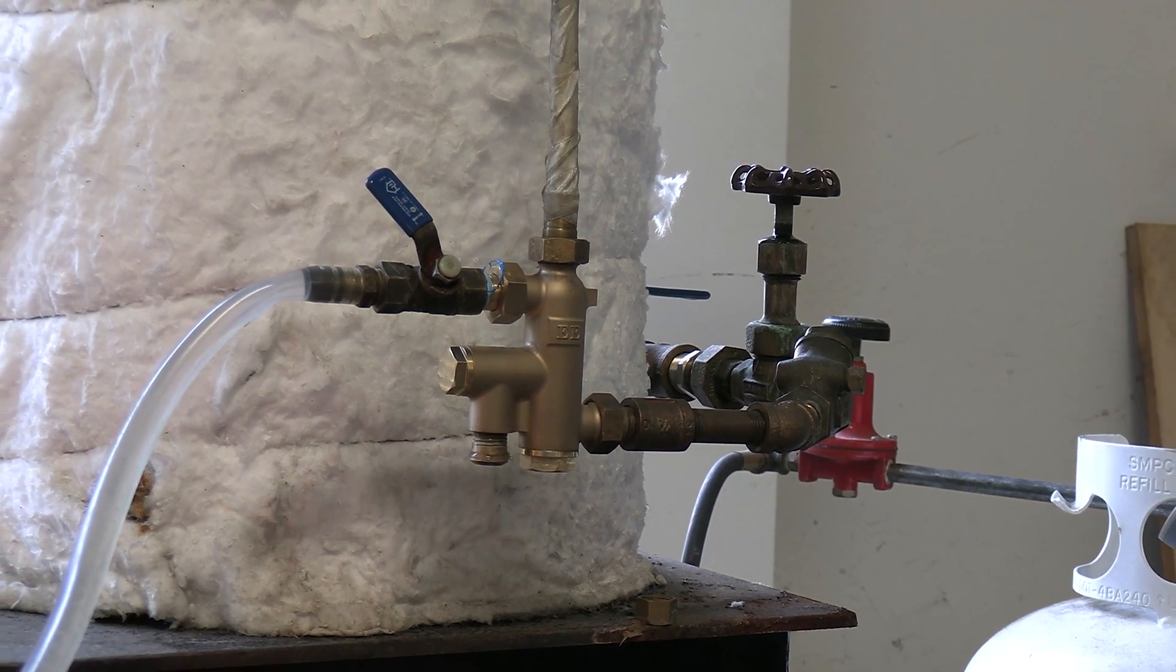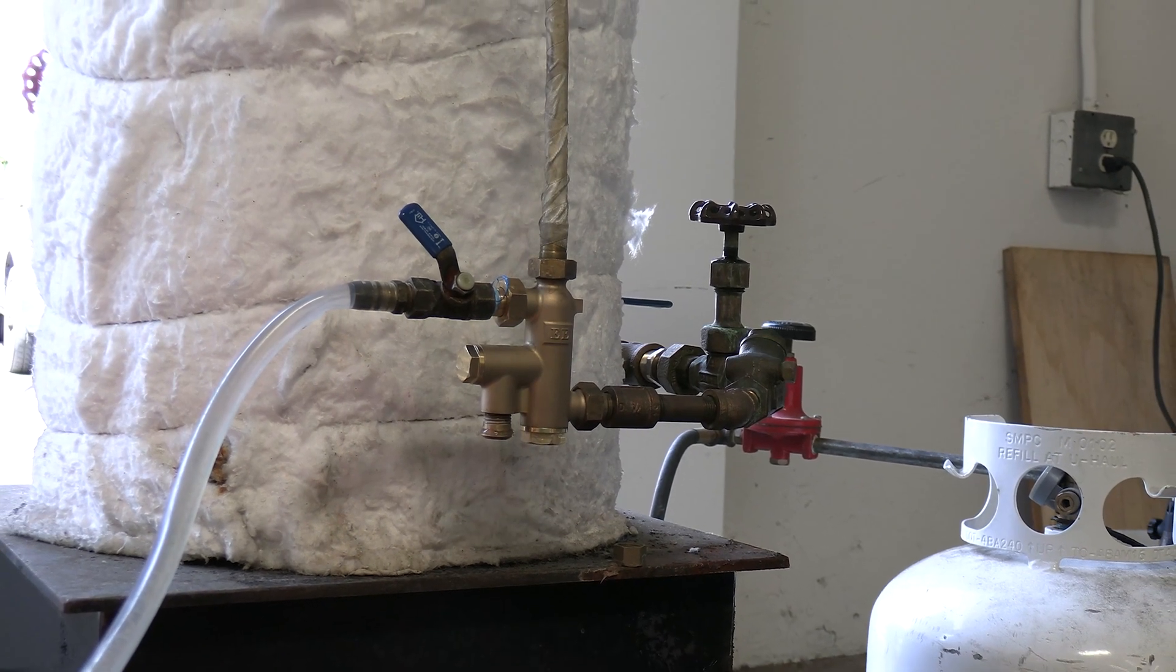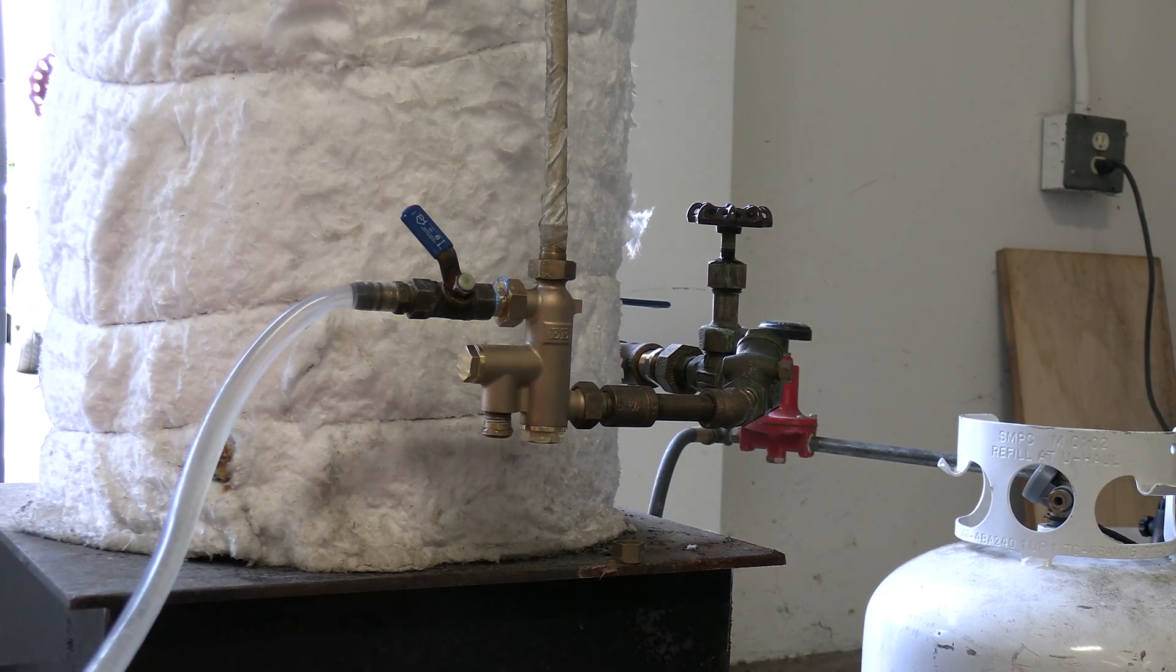Quick comment before we begin, when troubleshooting an injector, always have the steam valve wide open. Throttling or regulating the steam valve only makes troubleshooting more difficult. Alright, let the torture begin.